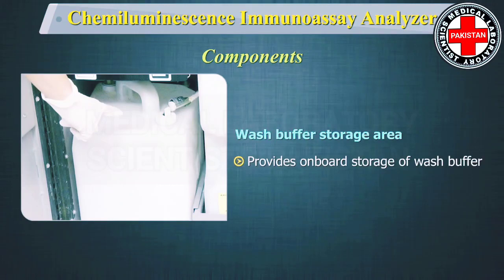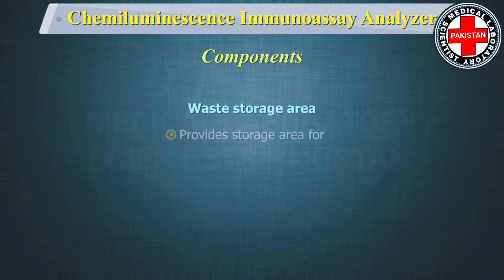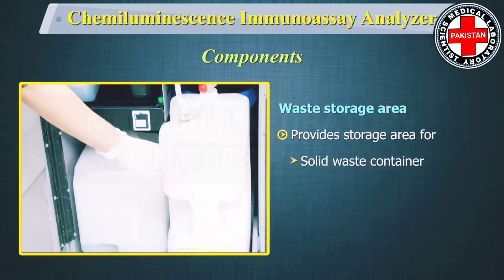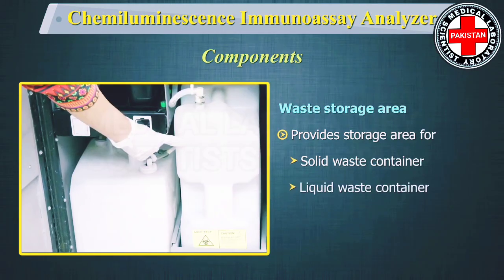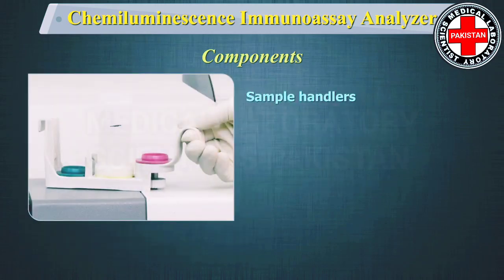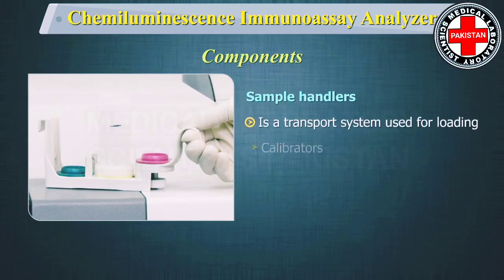The supply and waste center is the on-board storage area for bulk solutions and waste. The wash buffer storage area provides on-board storage of wash buffer. The waste storage area holds the solid waste container for used reaction vessels and the liquid waste container, accessed by sliding out the waste drawer. The sample handler is a transport system used for loading calibrators, controls, and patient samples and presenting them to the processing module.